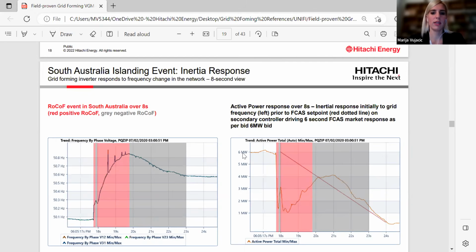You can see here that the battery energy storage system was discharging at around 6 megawatt, and upon the disconnection of the interconnector between two states, which was followed by this positive RoCoF event, the battery energy storage system actually immediately reduced the active power and then, as said before, mirrored the RoCoF event.